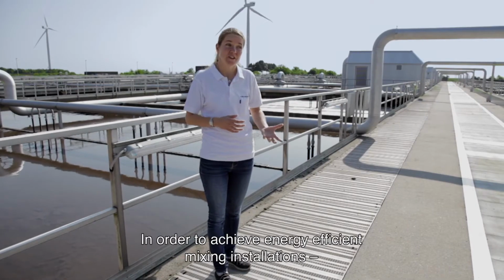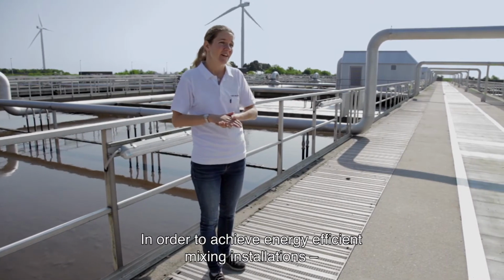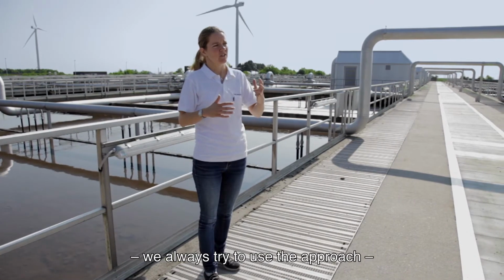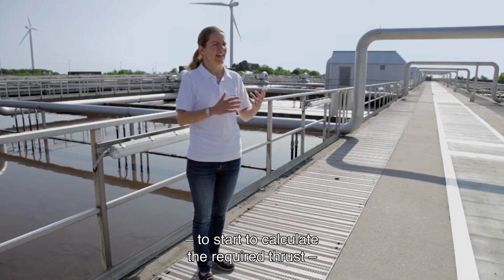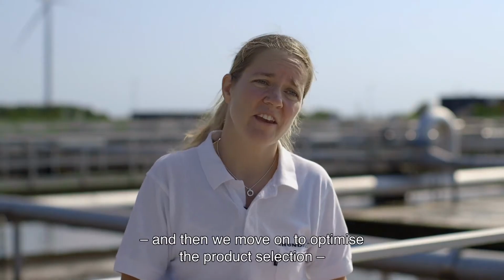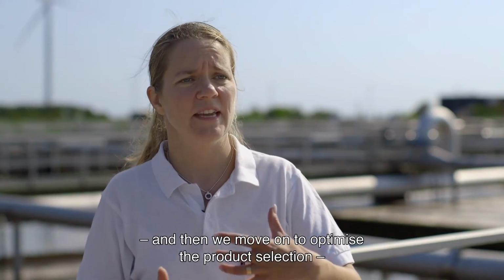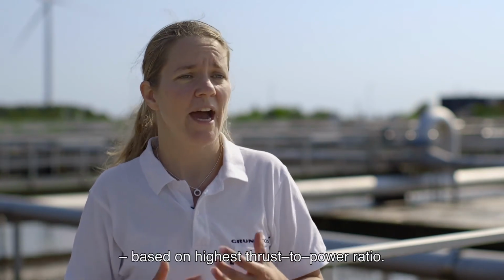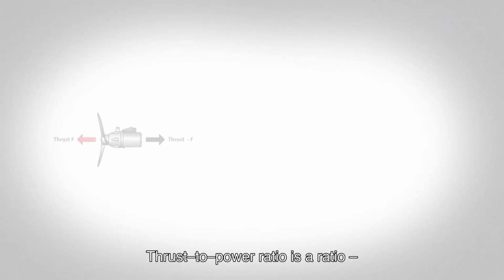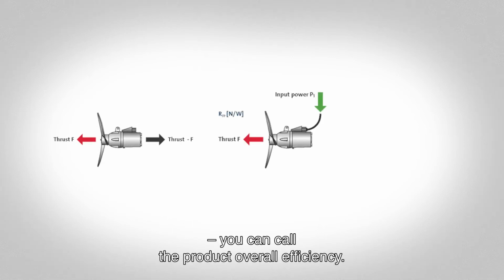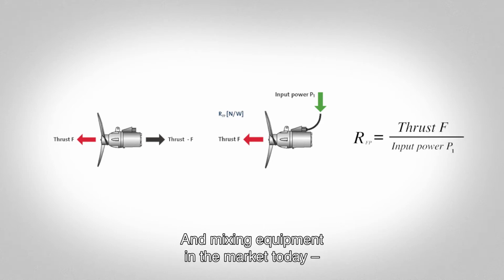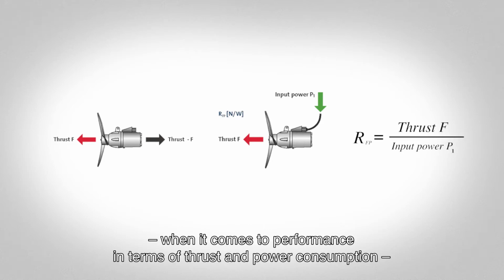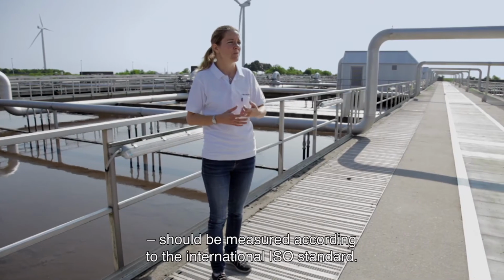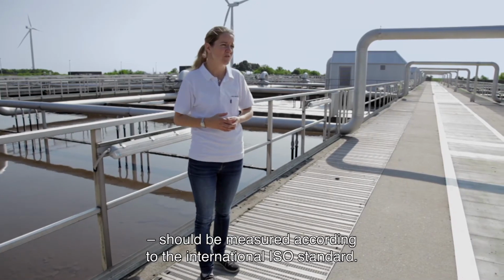In order to achieve energy-efficient mixing installations, we always try to use the approach to start to calculate the required thrust, and then we move on to optimize the product selection based on highest thrust-to-power ratio. Thrust-to-power ratio is a ratio you can call the product overall efficiency. And mixing equipment in the market today, when it comes to performance in terms of thrust and power consumption, should be measured according to the international ISO standard.